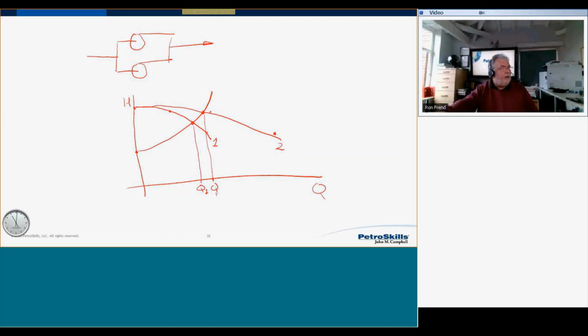That's your flow with one and two pumps operating together. So you might think by putting two pumps in parallel, you're going to get double the flow. You're not. And it really depends on the system head. So you think about your system curve, think about how much friction you've got in there. There is a way you could get double the flow.